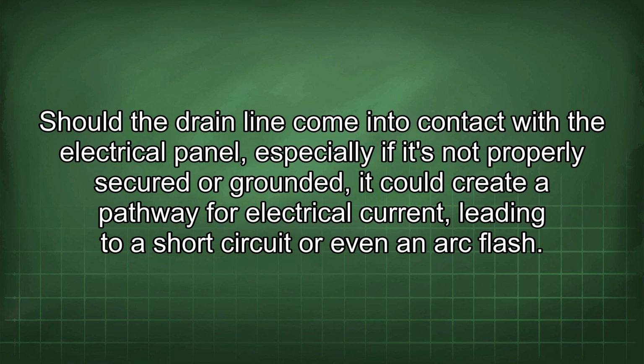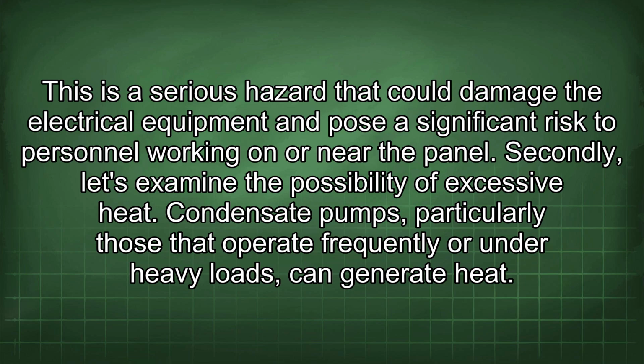Should the drain line come into contact with the electrical panel, especially if it's not properly secured or grounded, it could create a pathway for electrical current, leading to a short circuit or even an arc flash. This is a serious hazard that could damage the electrical equipment and pose a significant risk to personnel working on or near the panel. Secondly, let's examine the possibility of excessive heat.